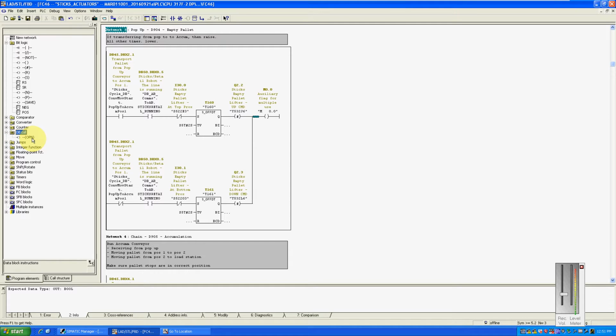I don't like using this, so a DB call. If you have data block 5 storing a whole bunch of pallet data, and it's DBB for DB byte 0, and DBB2, DBB4, you should address them in its full addressing as DB5.DBB0. If you get lazy, you can open up DB5 and then, because it's open in memory, just access that data as DBB0, DBB2, leaving off the DB5.